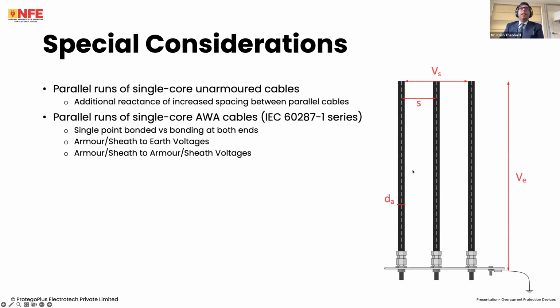Now, there are special considerations again, because when we have single core runs, we generally use either unarmored or armored. More common is armored, aluminium wire armored conductors. If we consider unarmored cables, the current carrying capacities are tabulated for a certain spacing between the conductors. But when we increase the spacing, we are affecting the inductance, effectively the reactance. So as you space them out more, the inductance increases, the reactance increases, the impedance increases. However, if we space them together, they are in effect grouped, so the current carrying capacity is reduced. So we have to strike a very close balance.